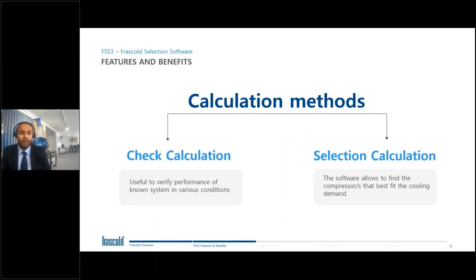FSS3 is structured into two main calculation methods or modalities, check calculation and selection calculation. With check calculation, it is possible to verify the performance of a known system. An example is if you already have a compressor in stock and you want to verify if this compressor can fit the requirements of a specific plant. Or maybe some operating conditions change and you want to check if, for this different condition, the compressor is still the best choice.